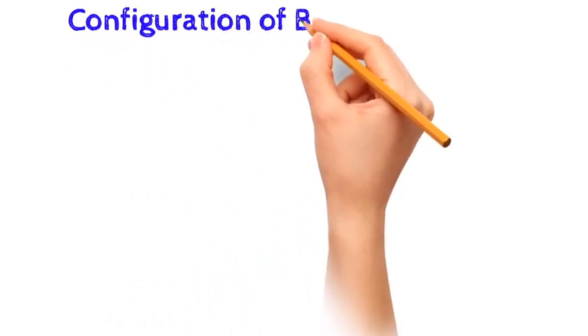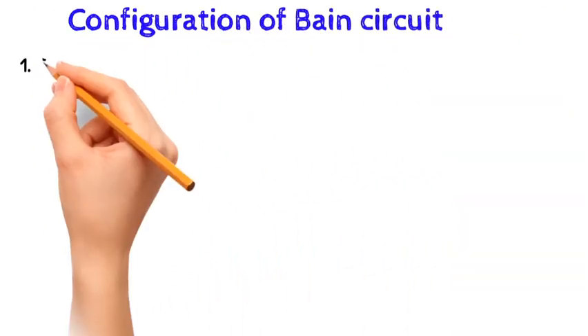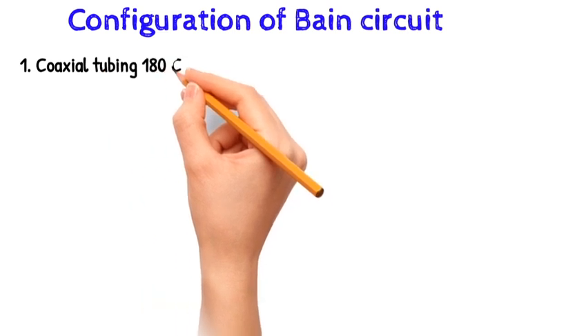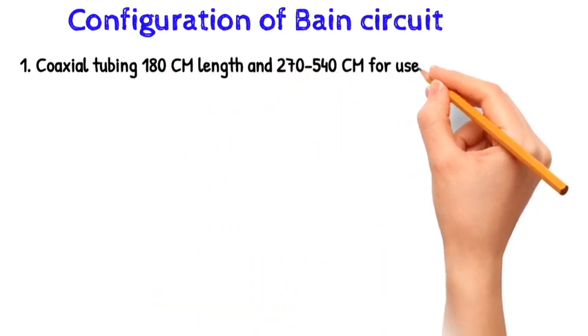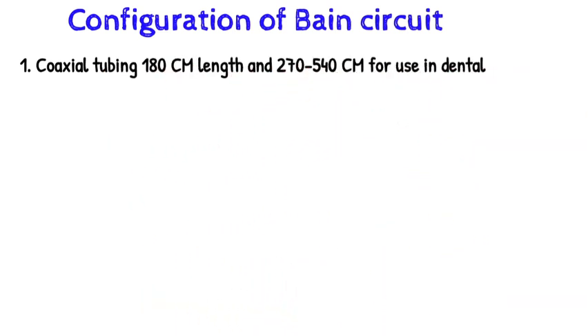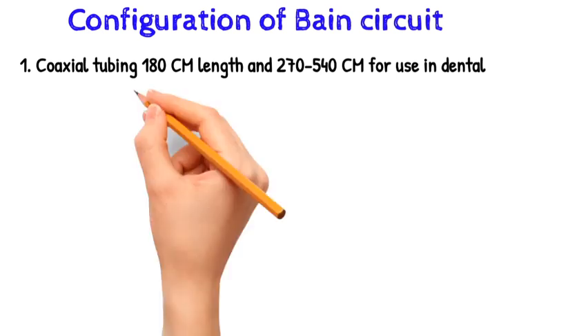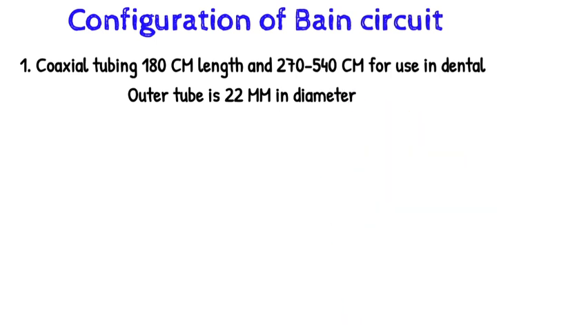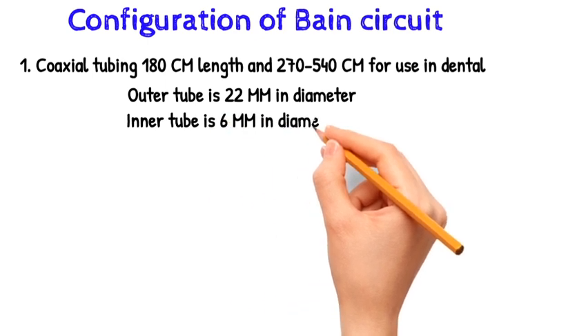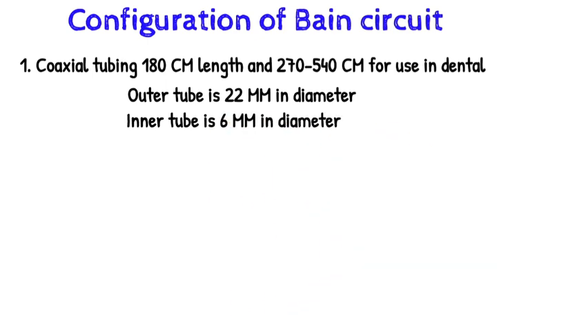Configuration of the Bain circuit: coaxial tubing is 180 cm in length, and 270 to 540 cm versions are used in dental, ophthalmic, and MRI suites. The outer tube is 22 mm in diameter and carries expiratory gases. The inner tube is 6 mm in diameter and carries inspiratory gases.